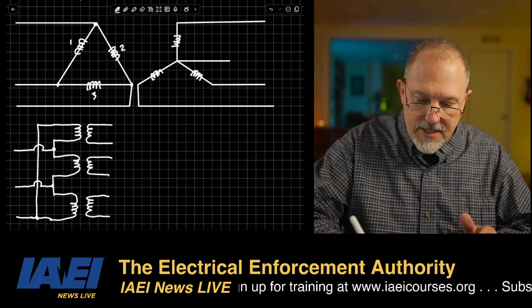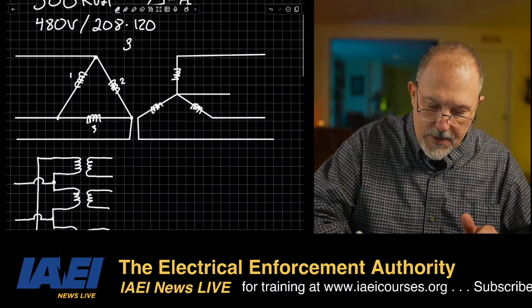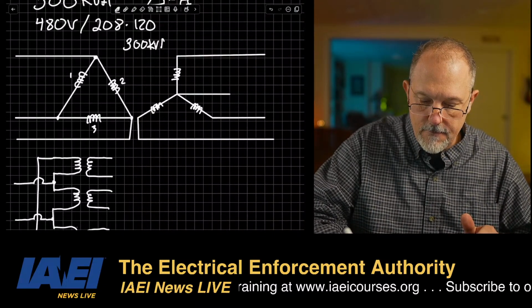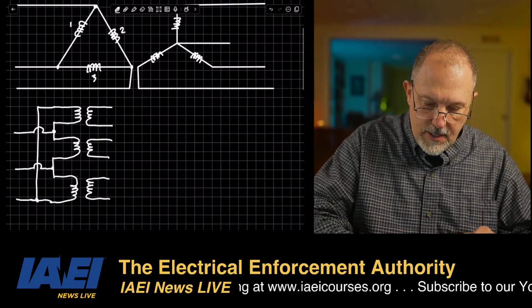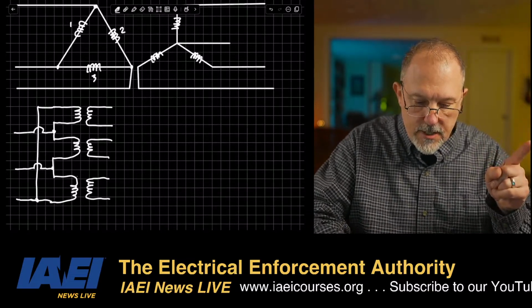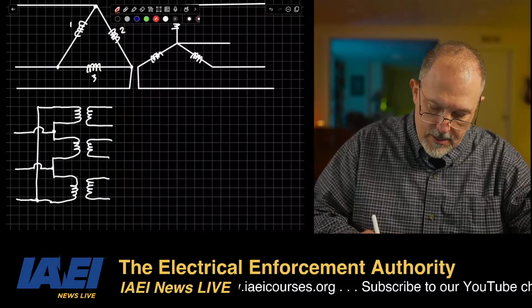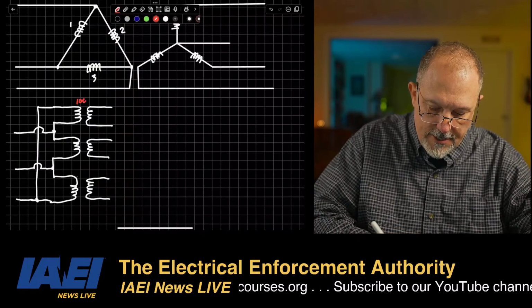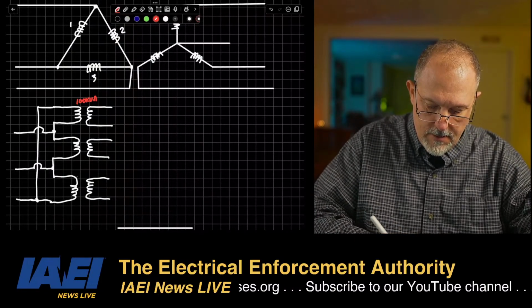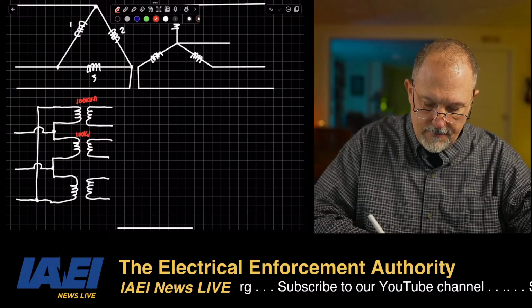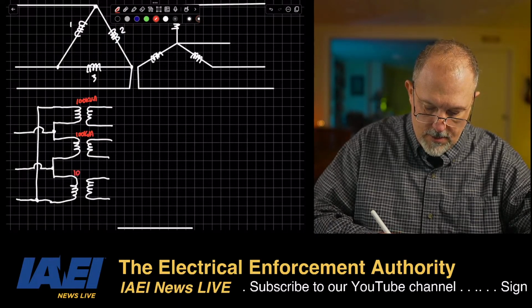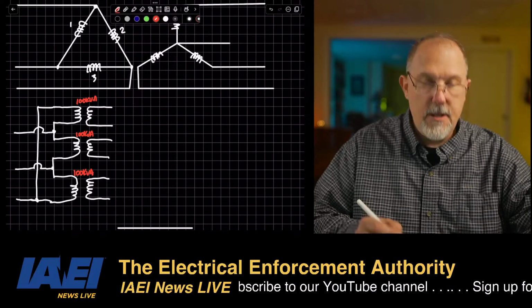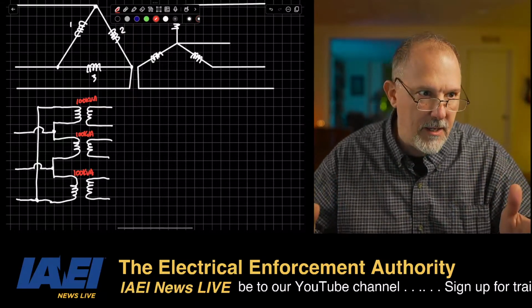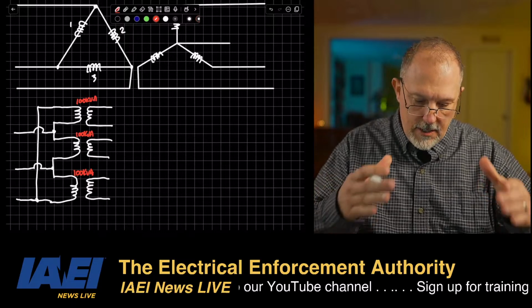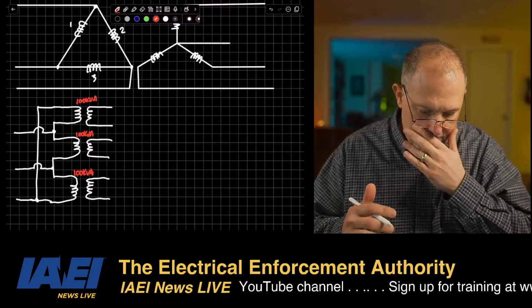Now we know if this is a 300 kVA bank, we know that each of these, and I'm going to change colors, I'm going to use red, we know that each of these is what? 100 kVA. So for a 3-phase bank, 300 kVA transformer, each transformer is 100 kVA.